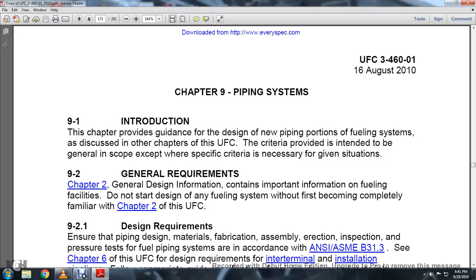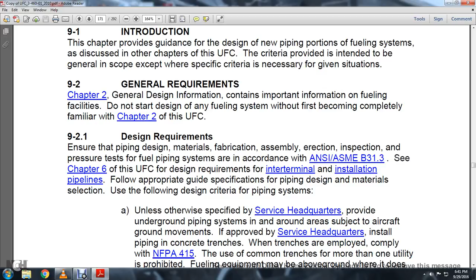9.2.1 Design Requirements. Ensure the piping design, material, fabrication, assembly, erection, inspection, and pressure test of the fuel piping system are in accordance with ANSI/ASME B31.3 and Chapter 6 of the UFC, design requirements for interterminal and installation pipelines. Use appropriate guidelines, specifications, piping design, and material selection using the following design criteria for the piping system, unless otherwise specified with the service headquarters.